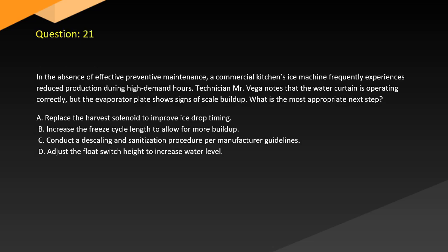Question 21. In the absence of effective preventive maintenance, a commercial kitchen's ice machine frequently experiences reduced production during high-demand hours. Technician Vega notes that the water curtain is operating correctly, but the evaporator plate shows signs of scale buildup. What is the most appropriate next step? A. Replace the harvest solenoid to improve ice drop timing. B. Increase the freeze cycle length to allow for more buildup. C. Conduct descaling and sanitization procedure per manufacturer guidelines. D. Adjust the float switch height to increase water level.